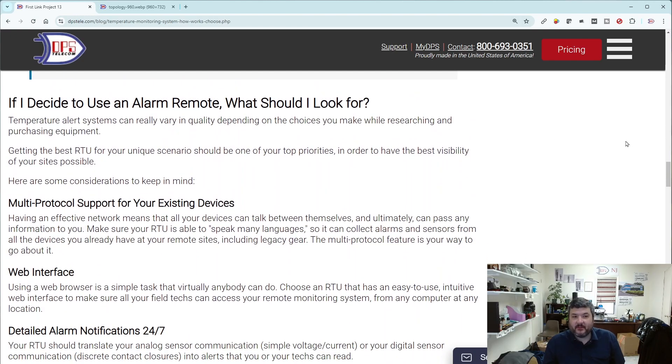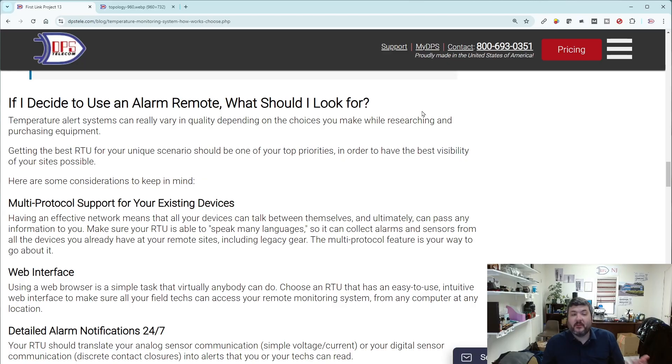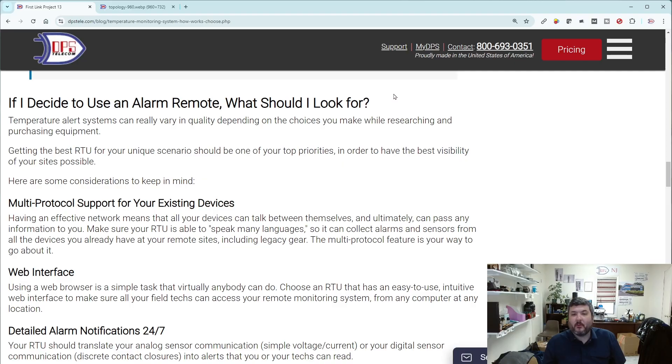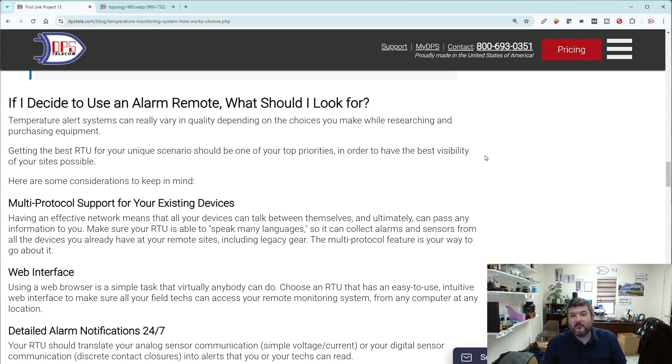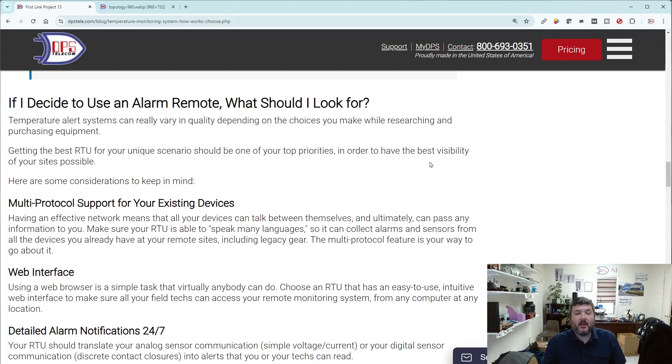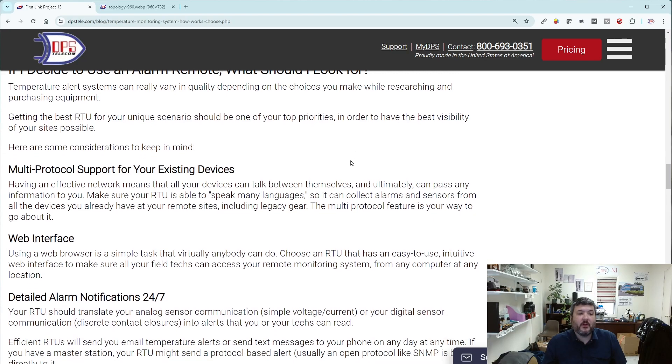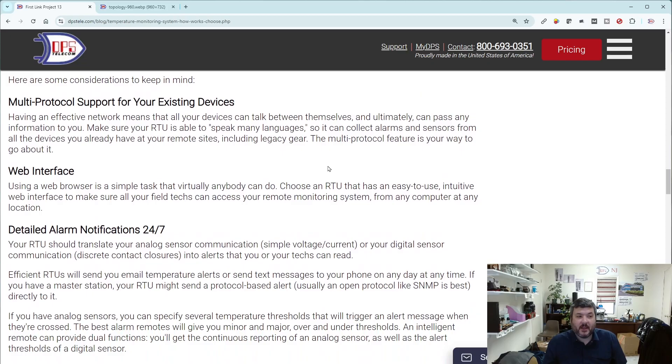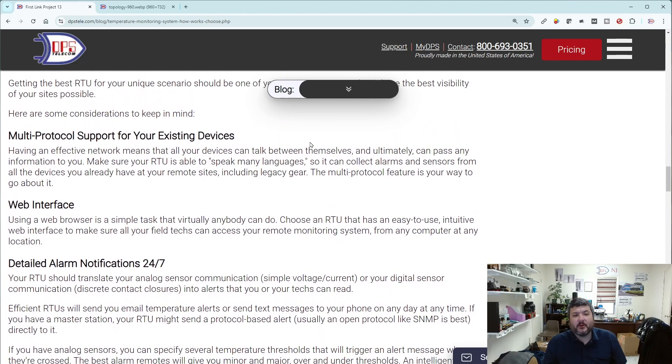Once we have these sensors, what do you need to look for as far as having an alarm remote or an RTU that's going to pull these things in? If you've done any research on the DPS website, we call those NetGuardians. Every manufacturer will have a different name, but the generic name for this is an alarm remote or a remote telemetry unit or sometimes remote terminal unit - RTU. If you have a sensor, it's not usually going to just be IP enabled on its own. It's probably going to need to go to some kind of a gateway device, which is what this RTU would be. What are some of the critical factors? It is important, whatever protocols are in play, whether you need to send SNMP to an SNMP manager or collect Modbus from a generator or talk to Modbus enabled sensors, make sure that RTU can cover those protocols.